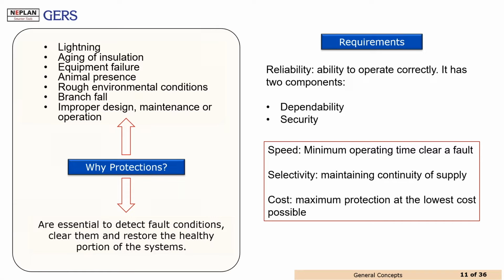However, they have some requirements in order to improve the reliability of the system, which has two components, dependability and security. We have to ensure that the protections work properly once any fault occurs. But we also have to ensure that the protection doesn't work improperly in different scenarios. Speed and selectivity are also taken into account for the different setting criteria. And for sure, the maximum protection at the lowest cost will always be one of the main goals.